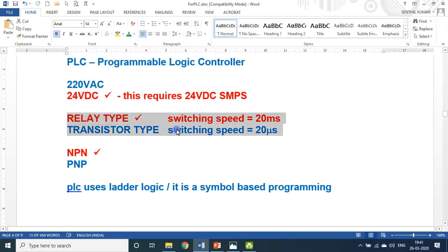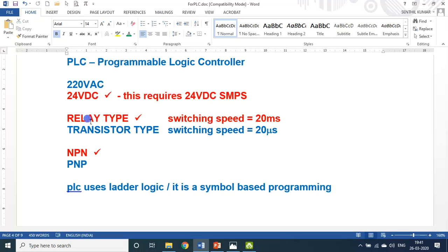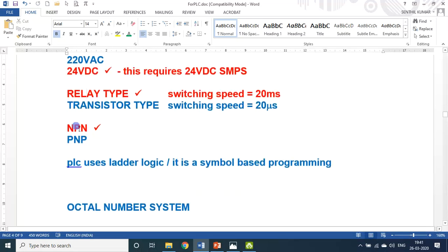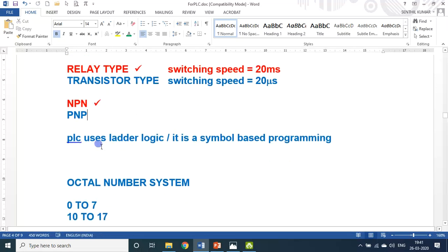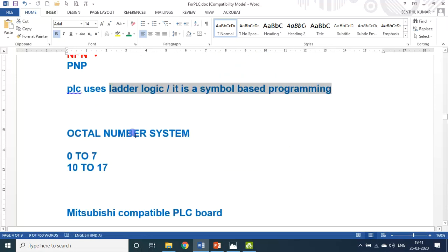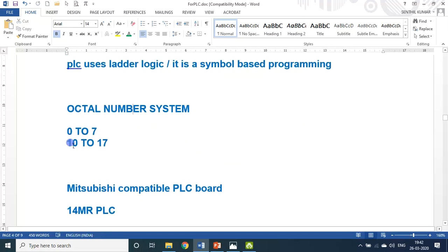There are two types of connectivity: relay type and transistor type. I prefer relay type because relay type can directly be connected with all the appliances — light, fan, motor, anything. The next category is between NPN and PNP. Largely, they use NPN type of PLC only, so I also choose NPN. PLC uses ladder logic — it is a symbol-based programming technique. It follows octal numbering: 0 to 7, 10 to 17, 20 to 27, and so on.